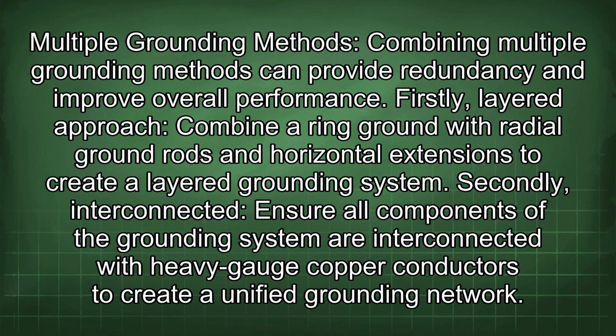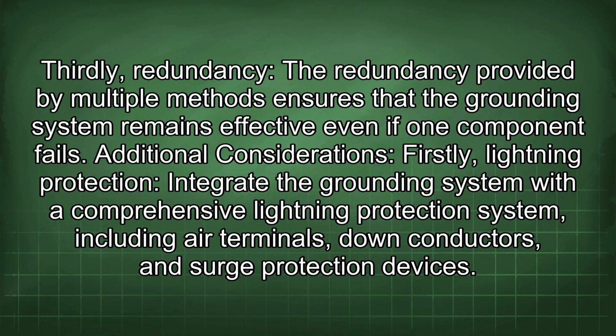6. Multiple grounding methods. Combining multiple grounding methods can provide redundancy and improve overall performance. Firstly, layered approach. Combine a ring ground with radial ground rods and horizontal extensions to create a layered grounding system. Secondly, interconnected. Ensure all components of the grounding system are interconnected with heavy gauge copper conductors to create a unified grounding network. Thirdly, redundancy. The redundancy provided by multiple methods ensures that the grounding system remains effective even if one component fails.